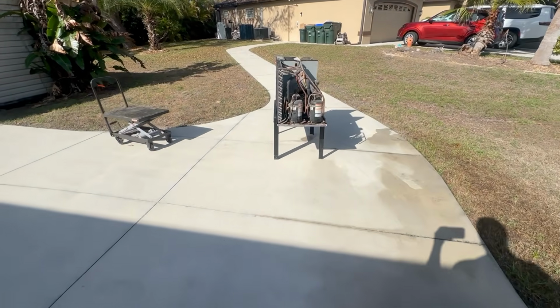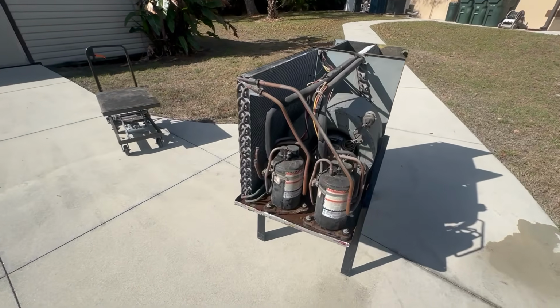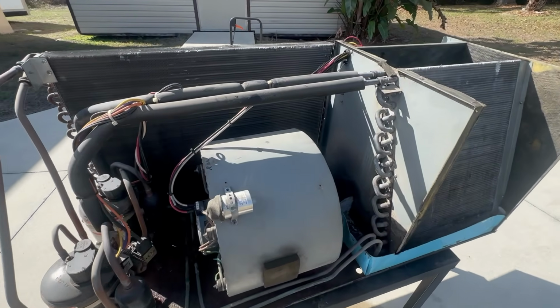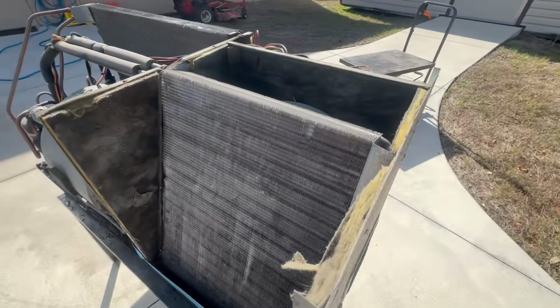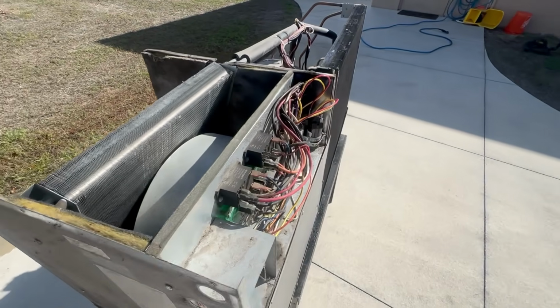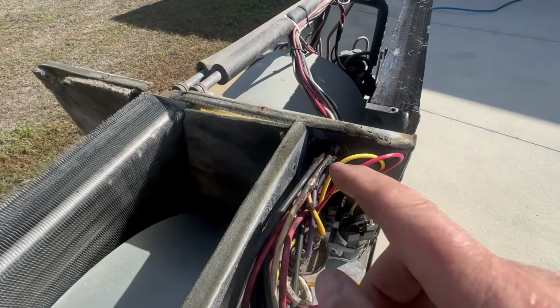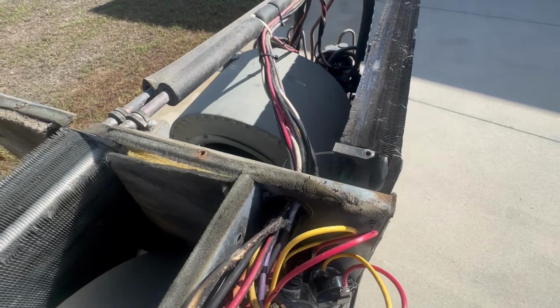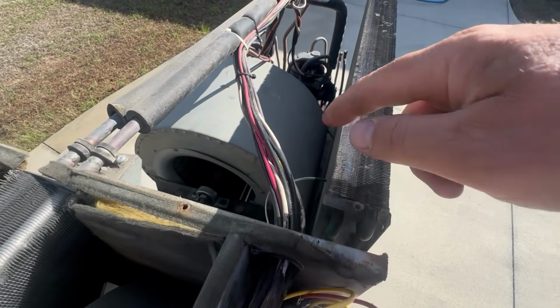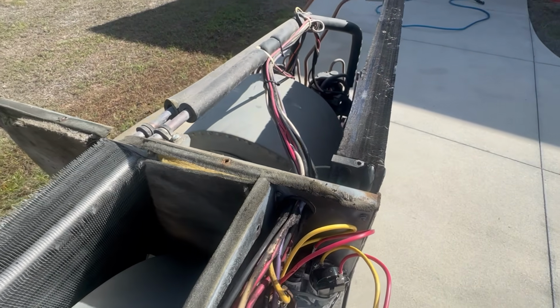So you can see I've got the unit already washed out and cleaned. It was pretty nasty. I did go ahead and update the wiring on this where that PTC had gone nuclear and melted a little bit of the wires, but they're still good. It did get the freeze sensor on the inside all melted, so we've changed it out.